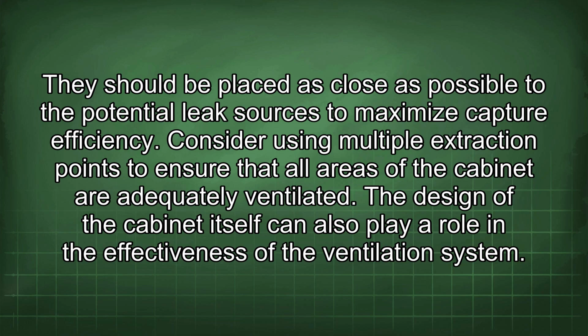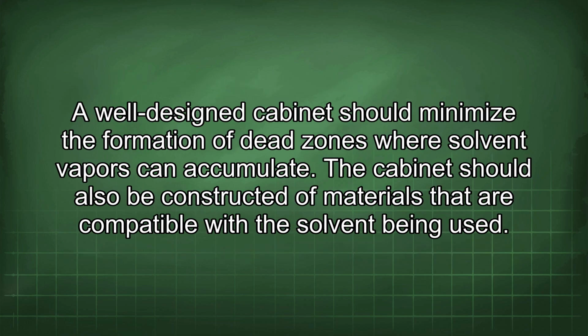They should be placed as close as possible to the potential leak sources to maximize capture efficiency. Consider using multiple extraction points to ensure that all areas of the cabinet are adequately ventilated. The design of the cabinet itself can also play a role in the effectiveness of the ventilation system. A well-designed cabinet should minimize the formation of dead zones where solvent vapors can accumulate. The cabinet should also be constructed of materials that are compatible with the solvent being used.